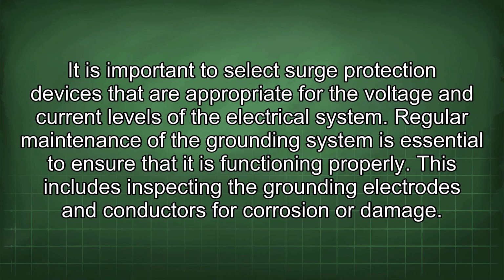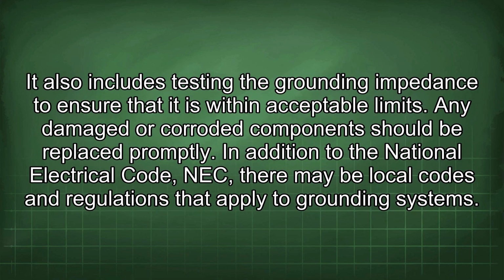Regular maintenance of the grounding system is essential to ensure that it is functioning properly. This includes inspecting the grounding electrodes and conductors for corrosion or damage. It also includes testing the grounding impedance to ensure that it is within acceptable limits. Any damaged or corroded component should be replaced promptly.